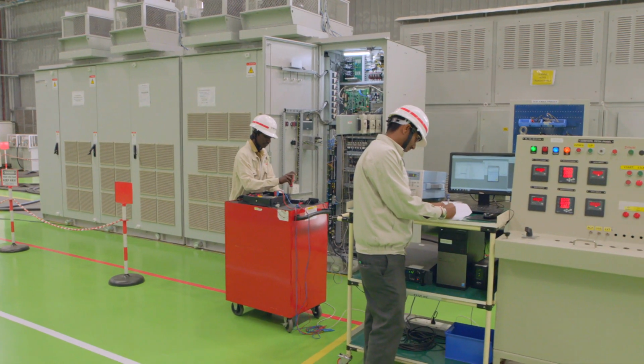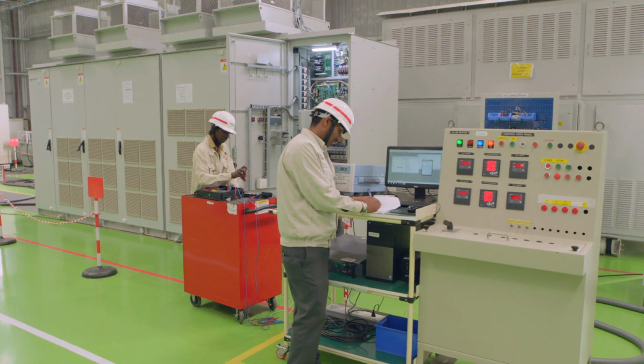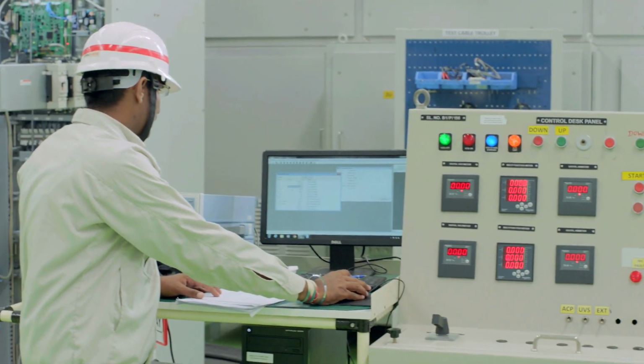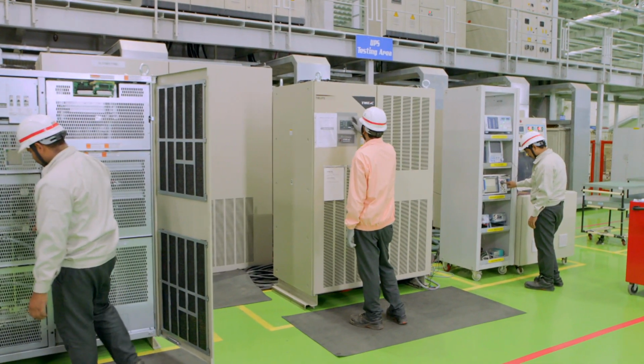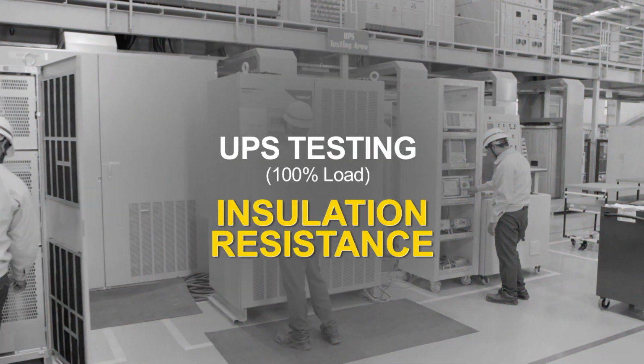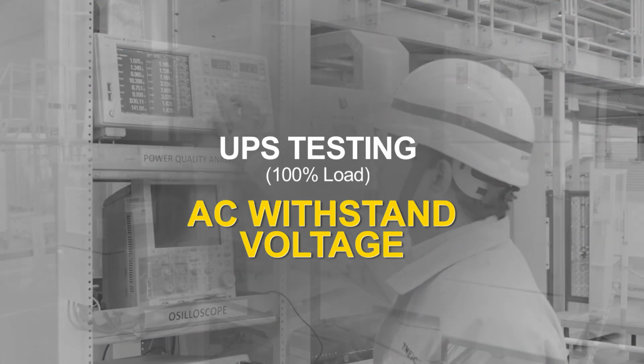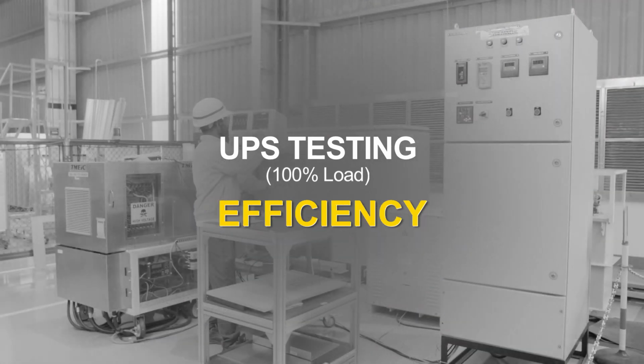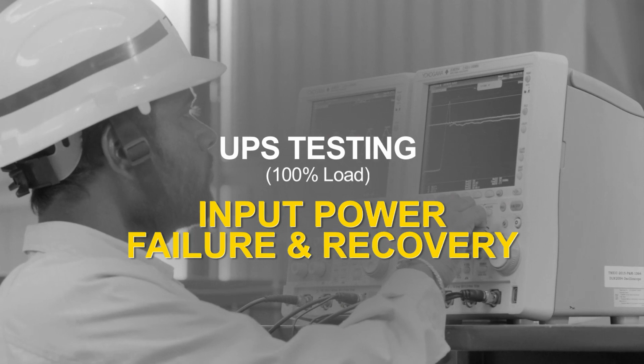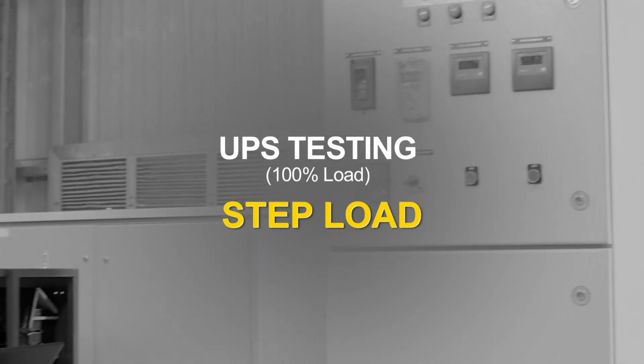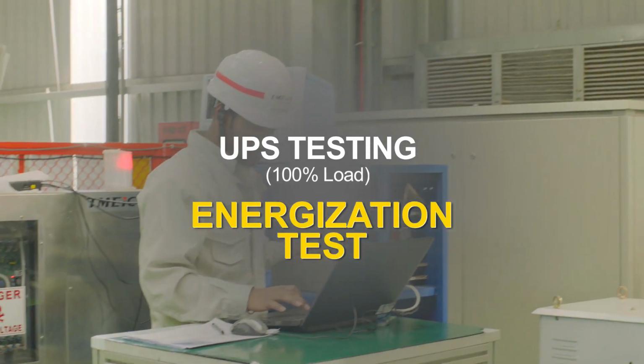We ensure drive reliability through 100% rated load test till temperature saturation. Every UPS is tested for insulation resistance, AC withstand voltage, control test, efficiency, input power failure and recovery, step load and energization test with 100% load.